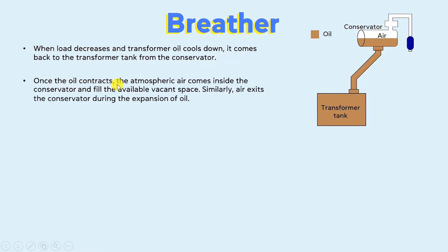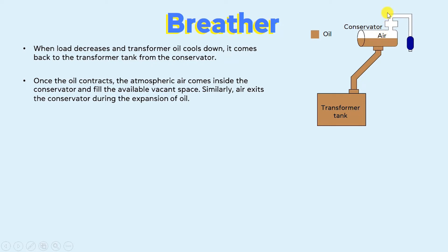Once the oil contracts, the atmospheric air comes inside the conservator and fills the available vacant space. During normal conditions, when the oil from the conservator comes back to the transformer tank, the vacant space in the conservator is fed by the atmospheric air. Similarly, air exits the conservator during the expansion of oil — when the transformer oil gets heated and expands, atmospheric air exits through the conservator.